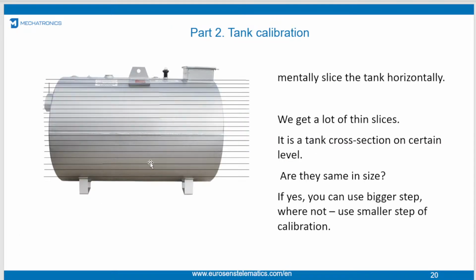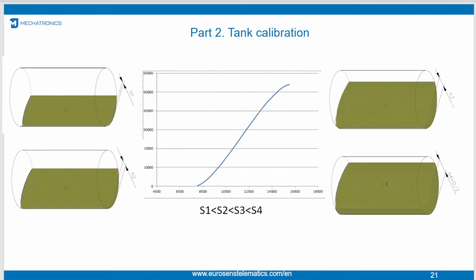In fact, a tank calibration chart can tell us about tank shape, and tank shape can tell us about the possible calibration chart. Look at the real tank first, then imagine that you have cut it into thin horizontal slices from left to right. That is the tank cross-section at different levels. Then ask yourself, do the slices have the same size? If you have slices of the same size, you can use a bigger step between tank calibration points. For a horizontal cylinder, we can't find sections of the same size. They're all different, so we can't reduce the number of calibration points for a horizontal cylinder.